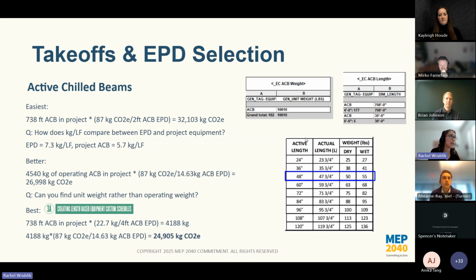Another way of doing it is doing a custom schedule in Revit. So that's this example here, adding up the weight and using that to then scale to that same EPD. The thing is, when you actually look at the schedule, it says operating weight and not equipment weight. So I did a quick Google search, finding the manufacturer data for the basis of design product, to see what the operating weight is versus the dry weight. If I use that, you see there's a slight difference there.